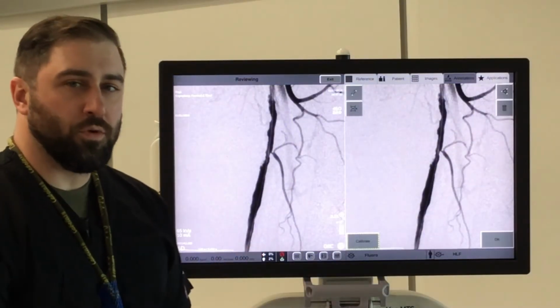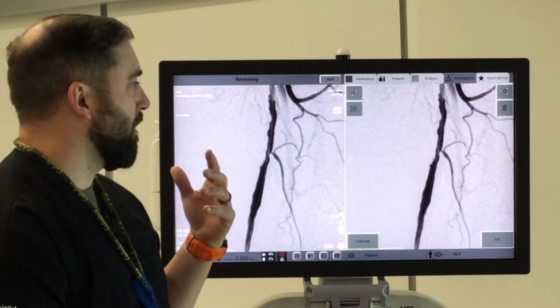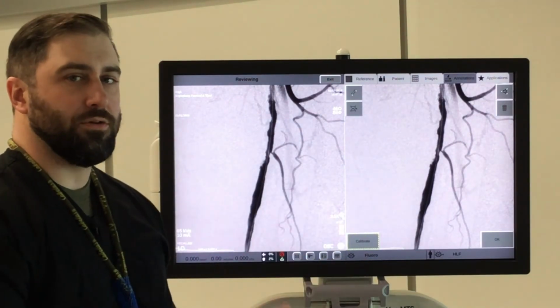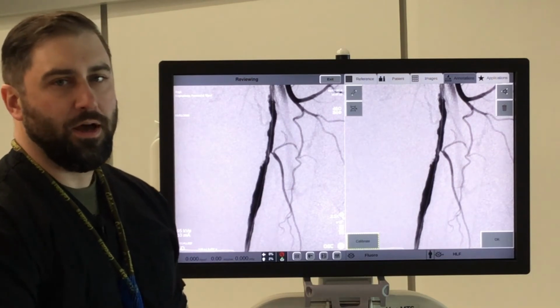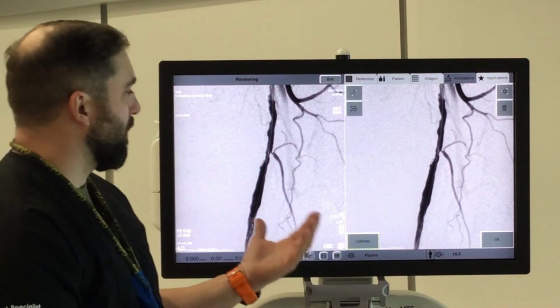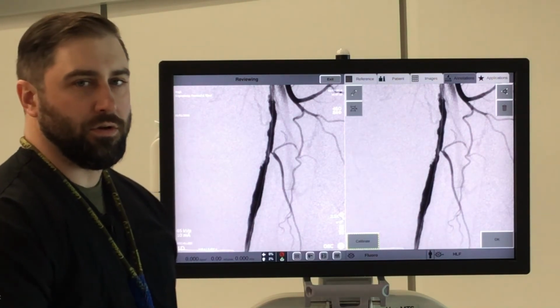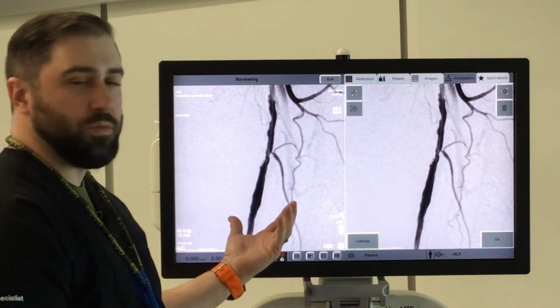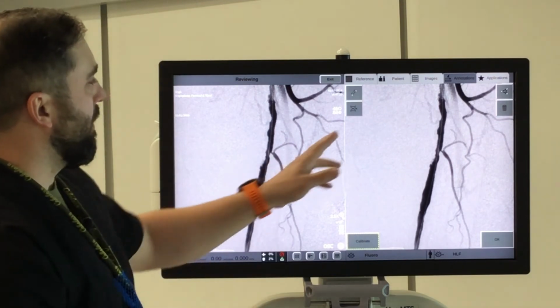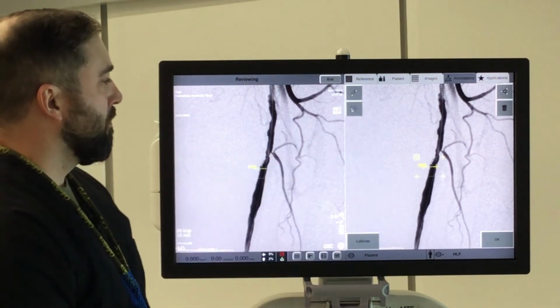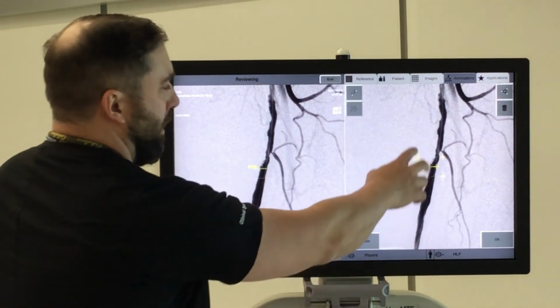The final measurement tool that we're going to work with here is going to be the stenosis measurement tool that allows you to measure a ratio of stenosis in a vessel. So what I'm going to do is I'm going to find my image here. I can also use the Live Zoom feature of the GE OEC Elite to zoom in on this picture here and blow it up really large.